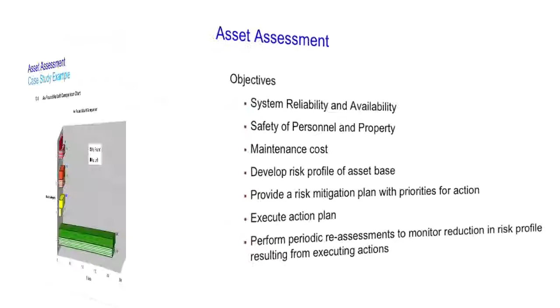These variables are inputted into a program, and with some algorithm programming it calculates the risk factor for failure. This is an output of one of the assessments we did at one of our customers. When we took the outage to do this assessment — I'll explain these bars — we have a before and an after. As we did the assessment, we were able to take it from a critical state, as it was found, do a little bit of PM, and move it into one of the other buckets.